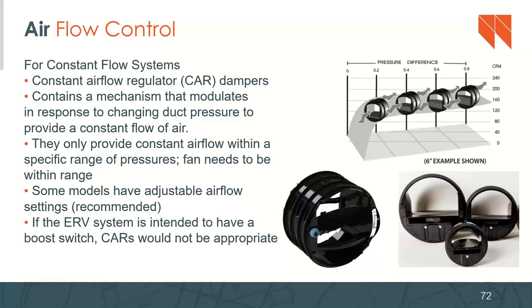Some models have an adjustable airflow setting, which we highly recommend. Sometimes slight, small adjustments are needed in the field. Even though these are constant airflow regulators, sometimes they are required to get these fine-tuned small adjustments in the field to hit Passive House spec. But yeah, they work great.